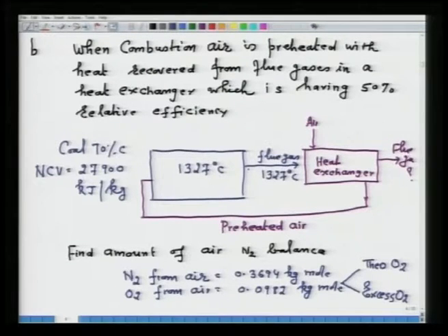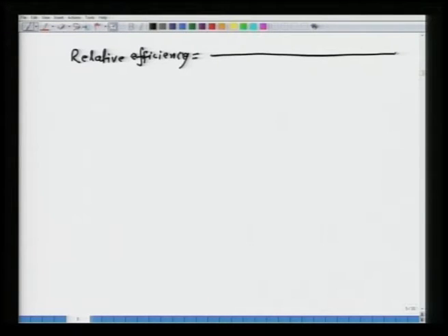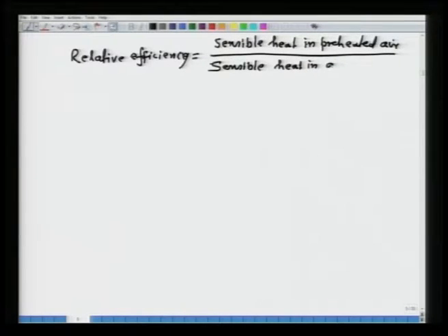So, next thing we can calculate now the relative efficiency. As already you know, that is equal to sensible heat in preheated air upon sensible heat in air at hot flue gas temperature.